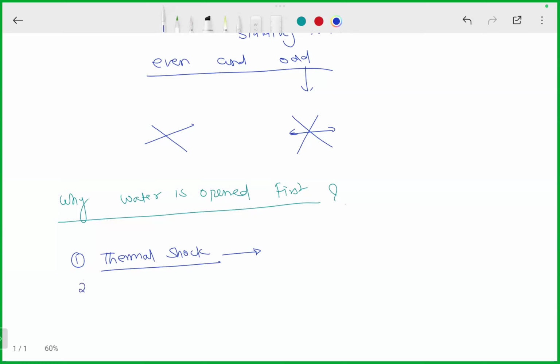Second, if you open vapors first and then admit water, there is a possibility of vapor lock. So the practice is to open the water first, let it fill the entire column gradually, and then open the steam, which presses the water down so it settles at the correct water level.